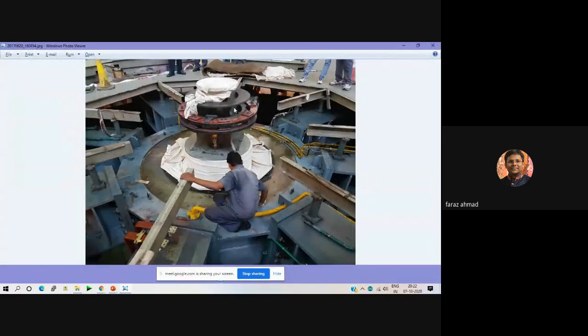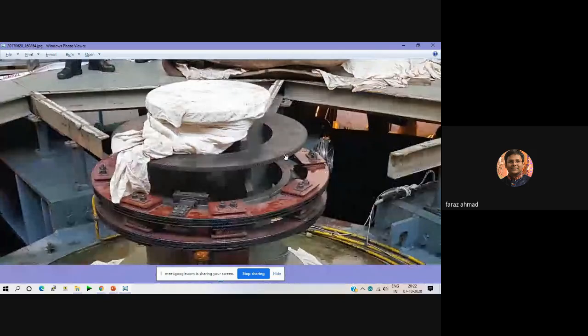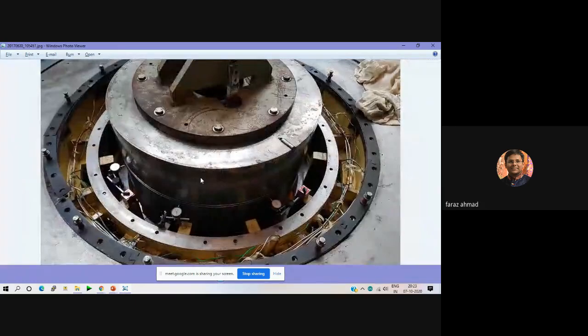So this is basically this. Teeth are used for counting. The number of teeth are counted on this whole ring. There is a sensor that is placed over here. It is a proximity sensor, a metallic proximity sensor. So it counts all the teeth. The number of rotations per second is obtained from this gear. There is a sensor that counts how many teeth have crossed through it in 1 second and accordingly gives the RPM of the machine. So this is for speed sensing.